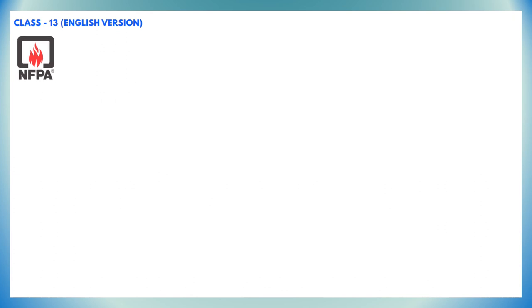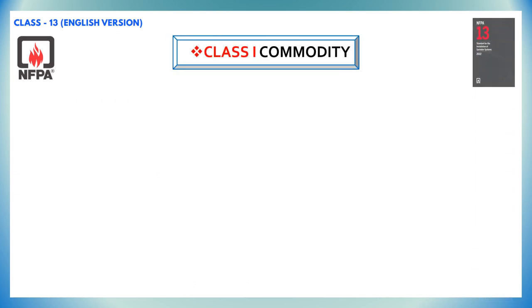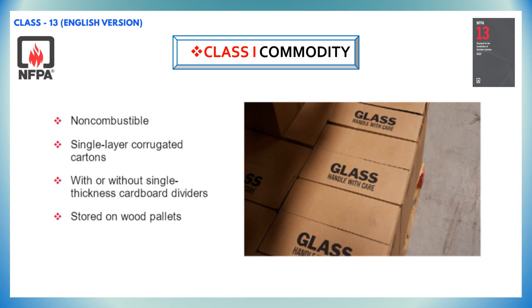Class 1 type commodity is defined as a non-combustible product that meets one of the following criteria. Class 1 commodity is placed directly on wood pallets, placed in single layer corrugated cardboard boxes with or without single thickness cardboard dividers, and shrink wrap or paper wrap as a unit load.